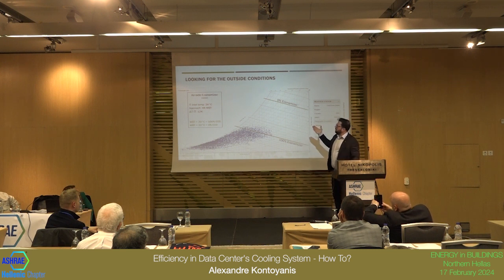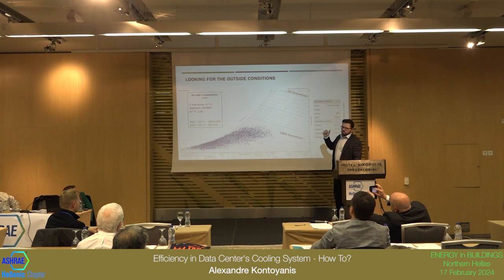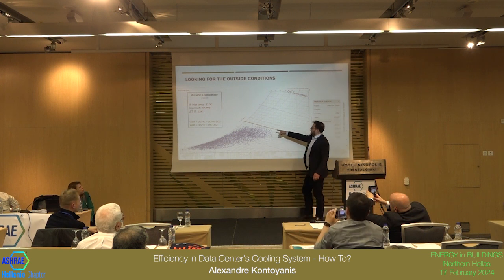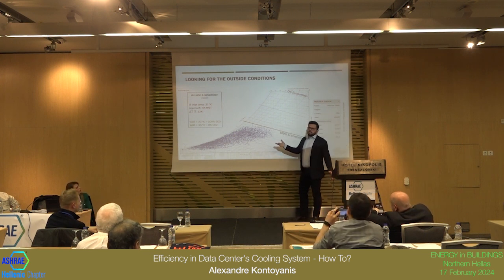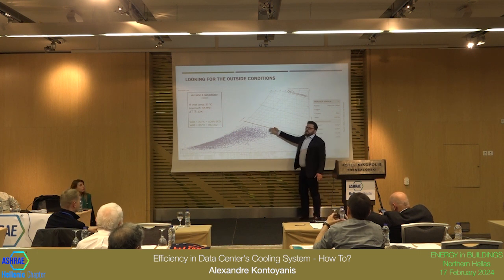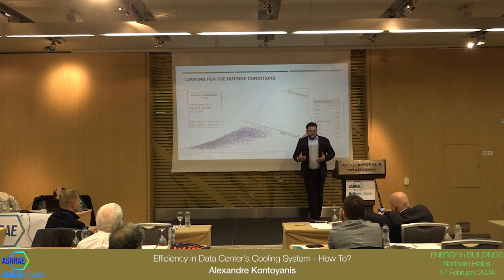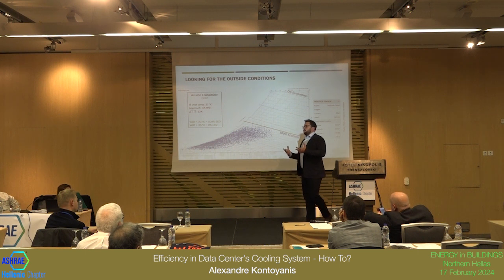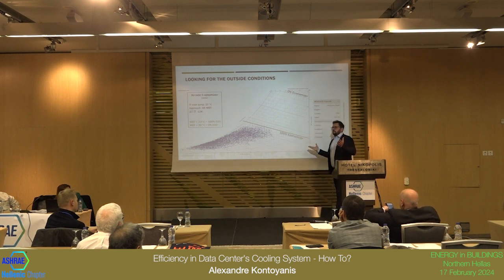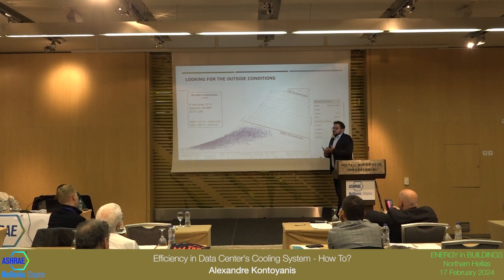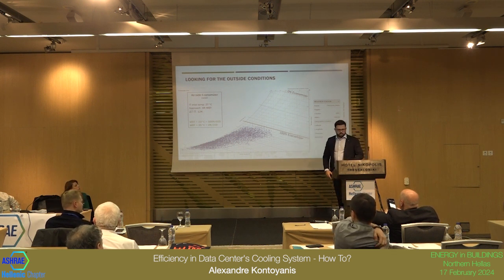If you raise your temperature even more, go to 27, still allowed, still recommended by the standard, I have only 4 hours and it's very close. It should fall in the allowable temperature range. What I'm saying is, new data centers in Thessaloniki should run without chillers. As a designer, I know it's hard to say this to your client, you do not need chillers, because you're in a very conservative industry. But here are the data. You can, and you should look for it.